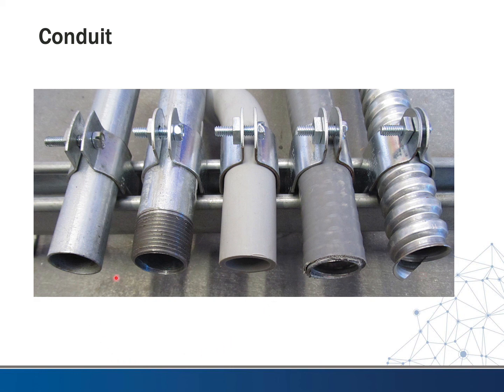Here is a comparison of all the conduit types side by side: flexible metallic conduit, liquid-tight flexible metallic conduit, PVC rigid non-metallic conduit, EMT, and what appears to be IMC or galvanized rigid conduit — it looks shiny, suggesting it is the IMC. The best way to distinguish EMT from IMC or RMC is that rigid and intermediate metallic conduit will be threaded, while EMT will not. This is a useful comparison of what they all look like relative to each other.